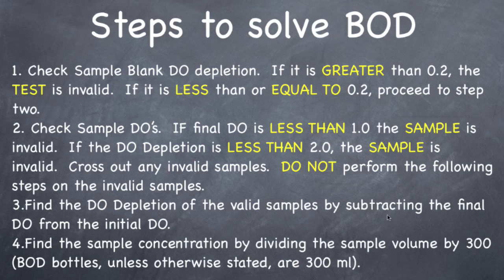Step 3: find the DO depletion of the valid samples by subtracting the final DO from the initial DO — so take your initial, subtract the final, and that's your DO depletion. Step 4: find the sample concentration — how concentrated is this sample — by dividing the sample volume by 300. BOD bottles, unless otherwise stated, are 300 mL. So on an influent sample, you would take about 6 mL of influent sample and fill the rest of the bottle with DI water to dilute it, because if you did straight influent, the BOD would deplete to almost nothing by the end of the test. That's how you find the sample concentration — divide the sample volume by 300 — and it'll be a percentage.